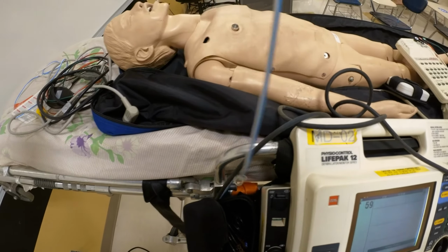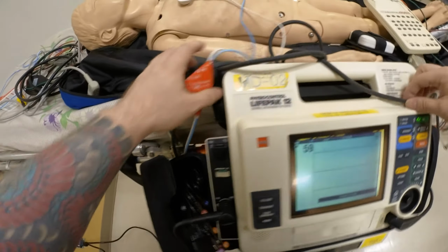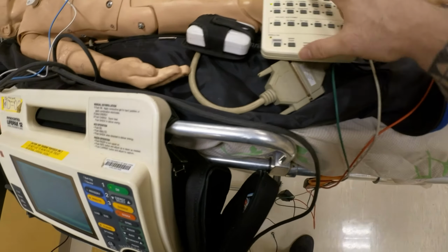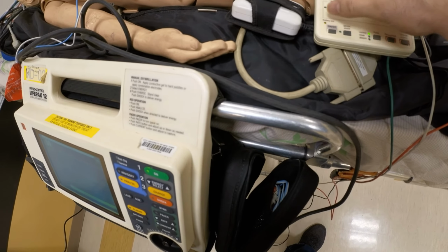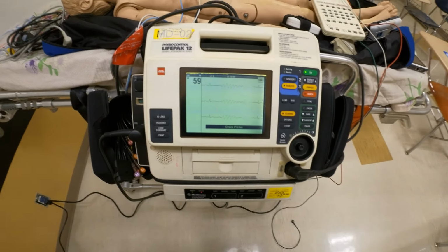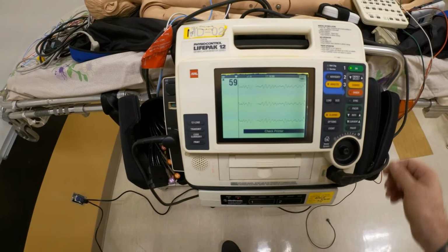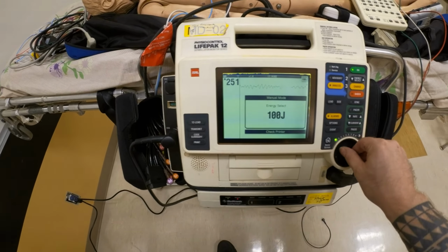Make sure you follow the diagrams, and what you want to also train the students to do, you want to hear this audible click. Right? If you do not hear the audible click, it's not going to function. So you're going to tell the students to have that in practice. So let's say I'm going to change this to ventricular fibrillation. So we see ventricular fibrillation. So let's see now if I'm able to deliver, right, the defibrillation here.